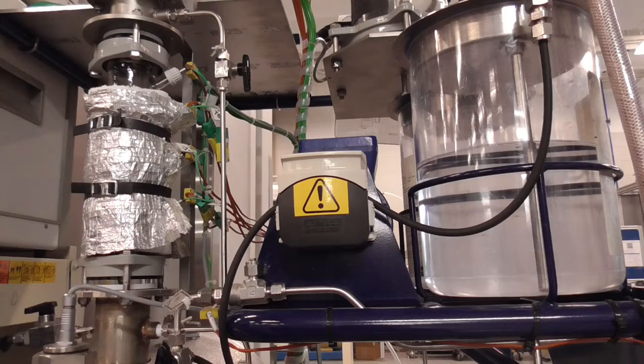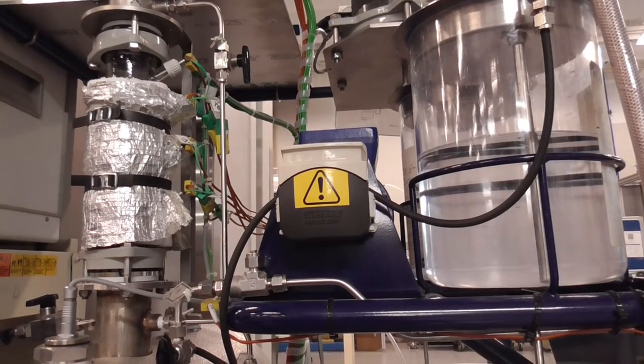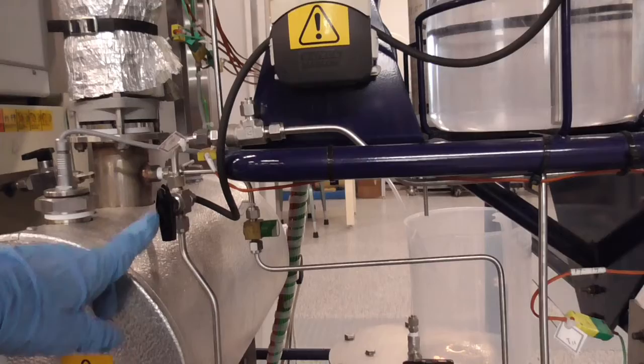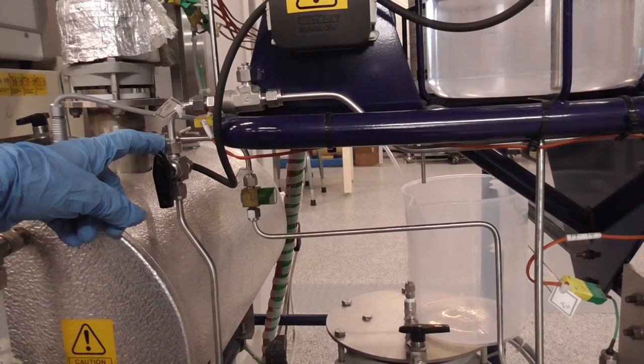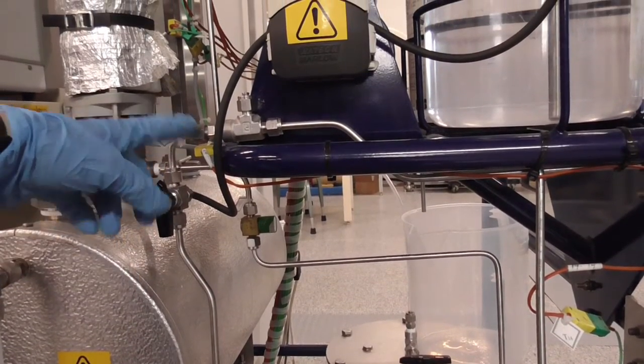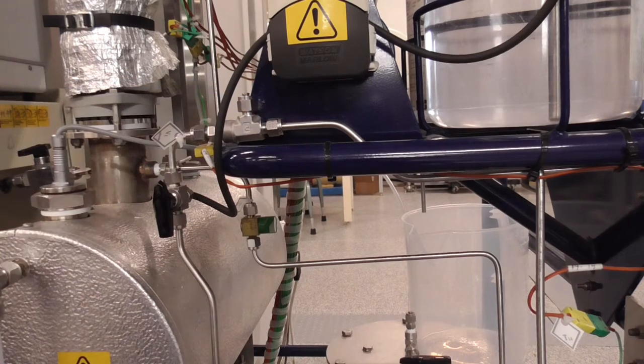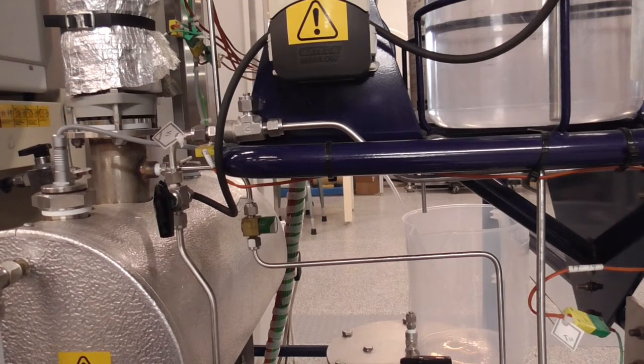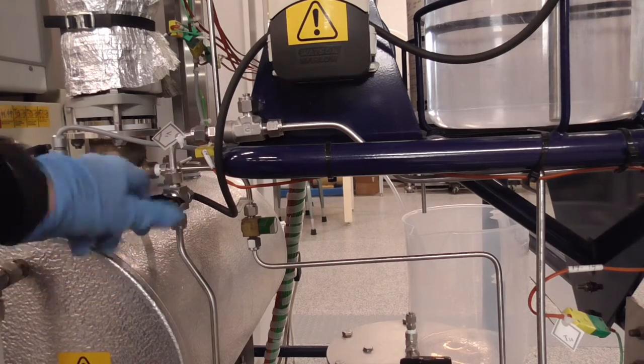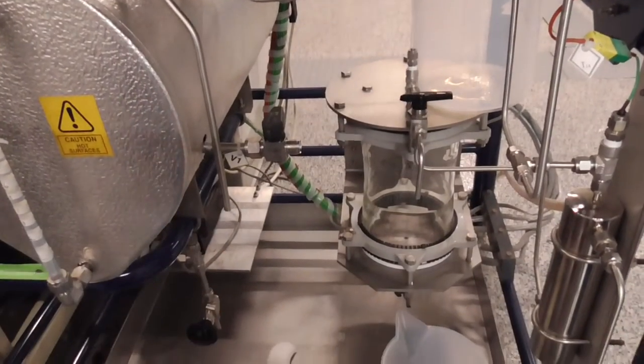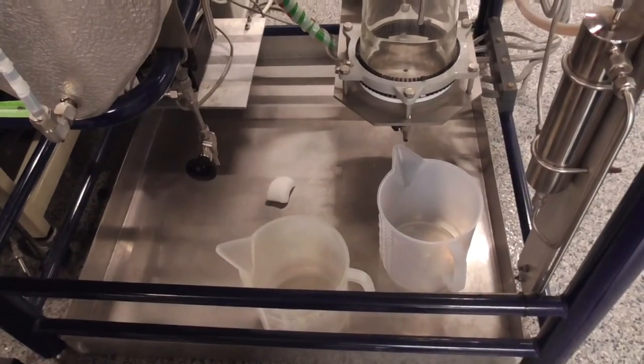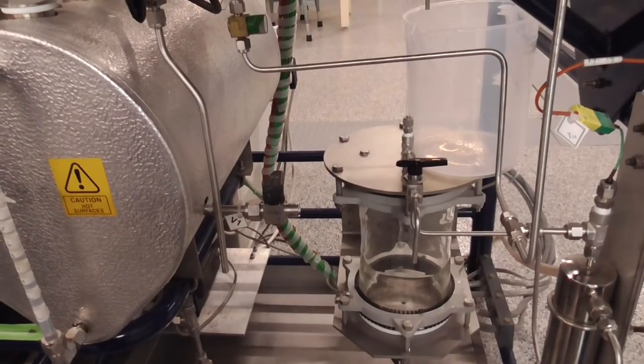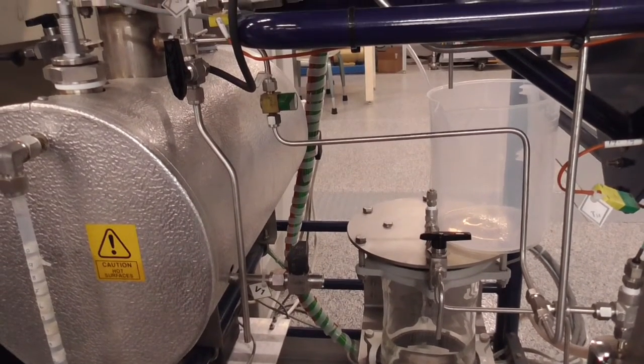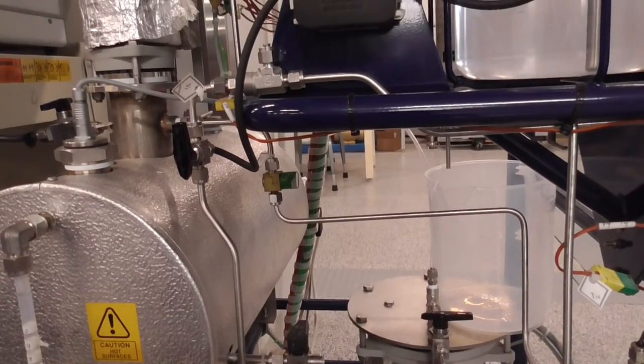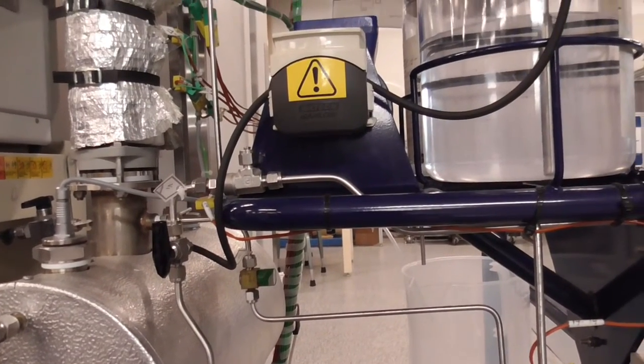So here is our feed tank and the peristaltic pump. This flows out of the pump then to this tubing. If this valve is pointing this way, it goes to the column by way of the heat exchanger. In order to calibrate the feed pump, we're going to turn it this way out, and the feed will then drop out of this tube and into the buckets below. You can then intercept that flow with a graduated cylinder and stopwatch and see what the flow rate of the peristaltic pump is as a function of RPM.